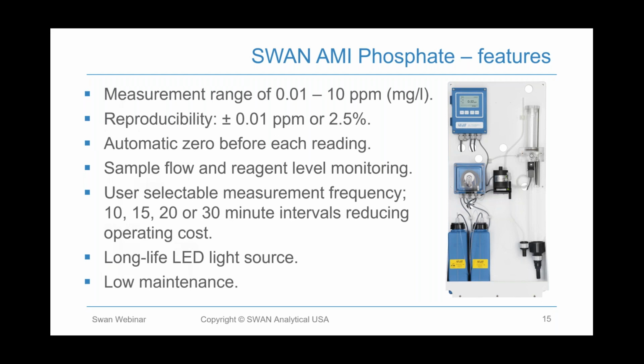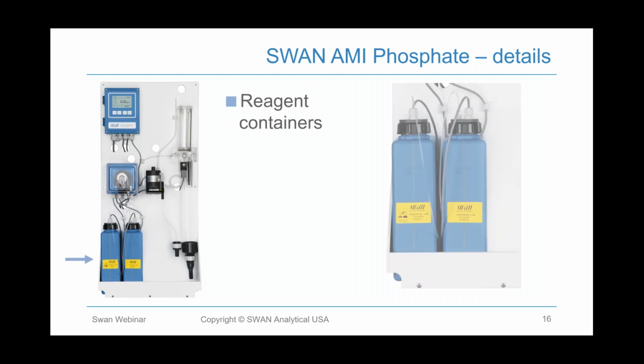So let's dig in just a little bit. I wanted to highlight a couple of the parts of the analyzer. If this is the first time you're seeing it, down there on the bottom are the reagent containers. Those are smart dip tubes that you see there on the top. The small tubing is the delivery part, and you see the connection there at the top of the unit.